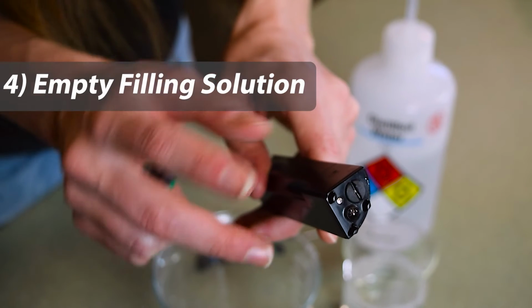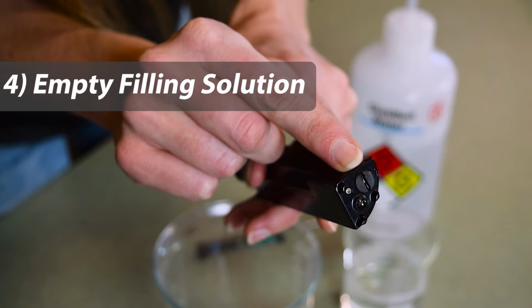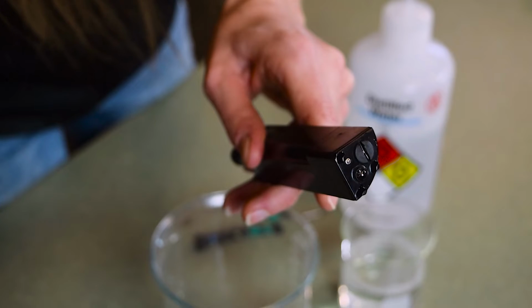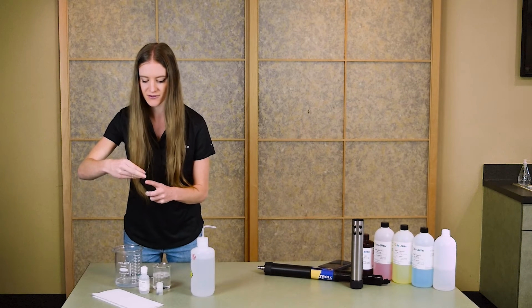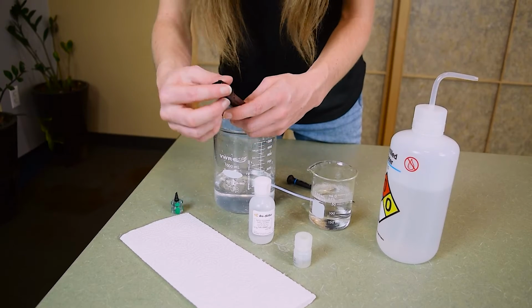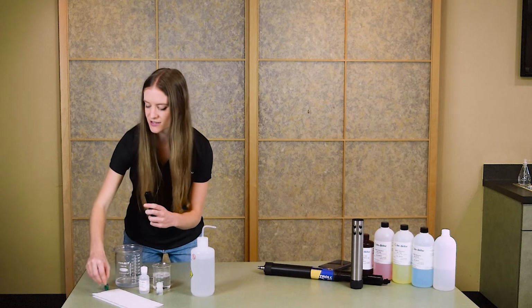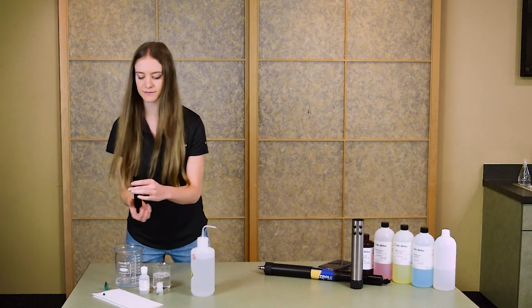In order to get to the filling solution, you'll need to remove the reference junction, which kind of looks like this flathead screw on the surface of the sensor. Use a flathead screwdriver to unscrew the reference junction. If you're just performing routine maintenance, you can save the reference junction for later.